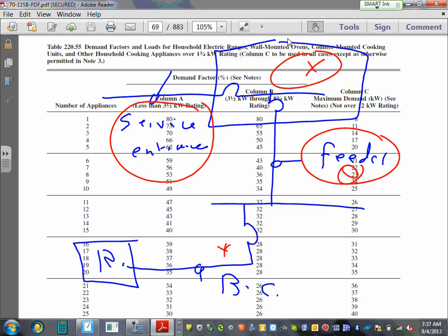So that's the whole idea of all these tables that we use in the NEC cookbook. Based on real experience and statistics, they came up with these tables that allow you to have smaller sizes because of what they call diversity of the load. It's highly unlikely that loads will be used at the same time. Can I get you to understand that concept behind this table and every table in the NEC cookbook? All the rating tables in the NEC cookbook are based on the likelihood that people, when it comes to load calculation, are not going to be using the equipment at the same time. Okay, so that's the whole concept.